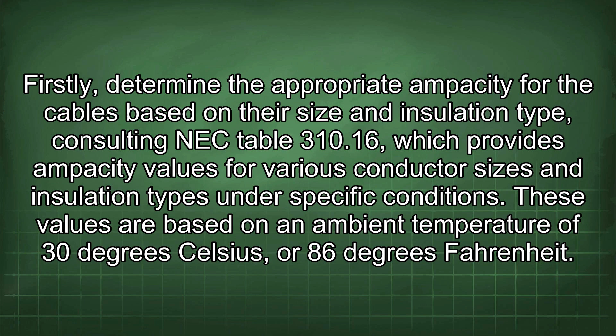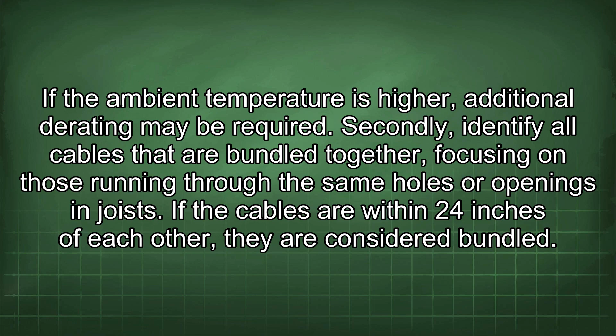Secondly, identify all cables that are bundled together, focusing on those running through the same holes or openings in joists. If the cables are within 24 inches of each other, they are considered bundled. Thirdly, apply the 20% derating factor to the ampacity of each bundled cable. To do this, multiply the ampacity value from NEC Table 310.16 by 0.8. The resulting value is the derated ampacity for the cable.